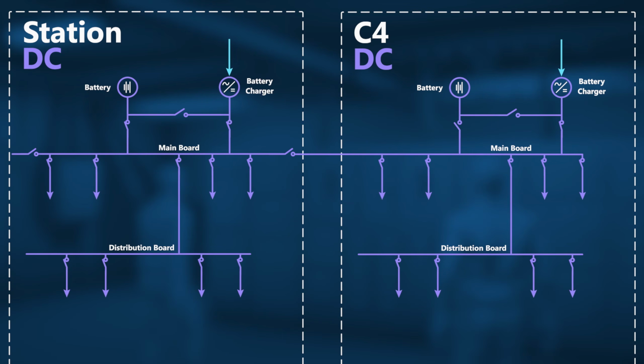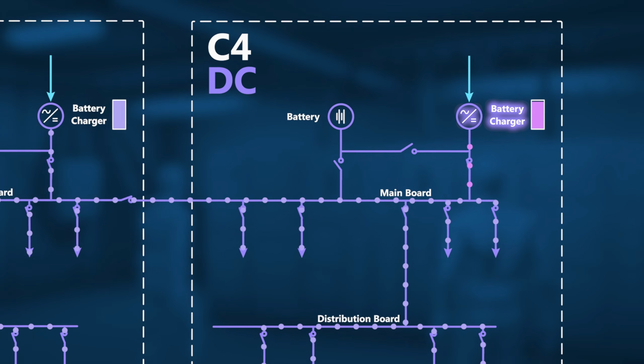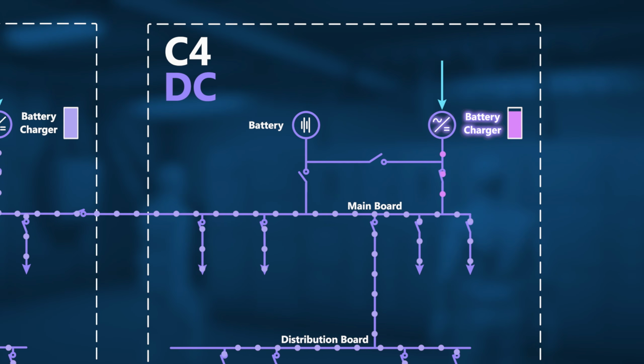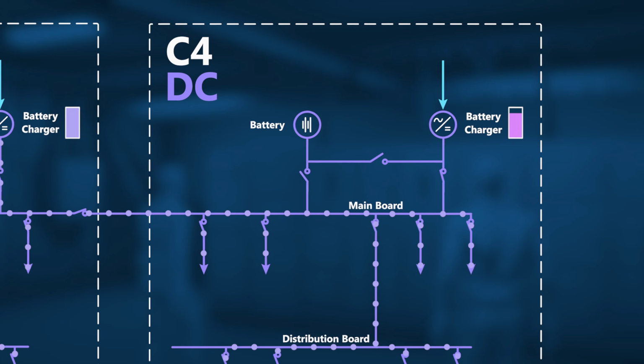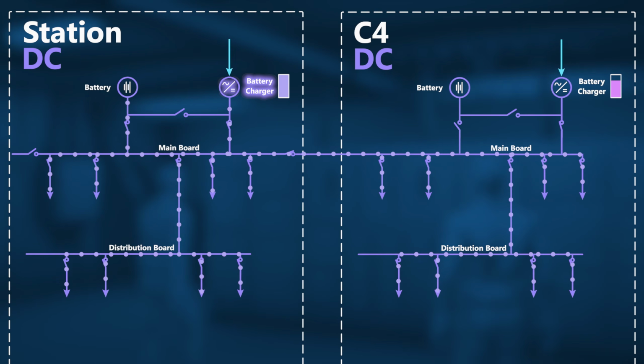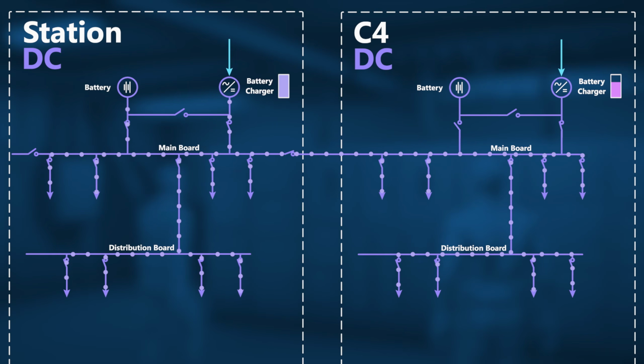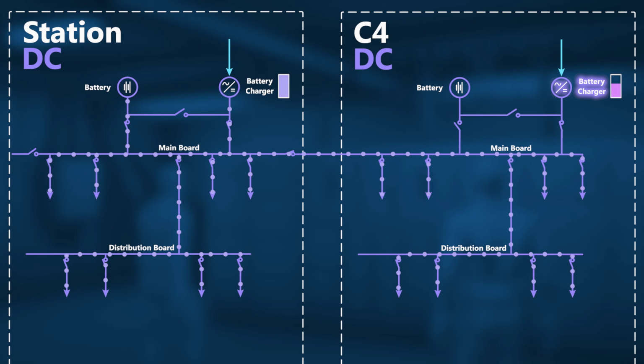To understand why, let's look at how the C4 and station battery chargers behave when they're connected to the same system. Before being connected, each battery charger maintains the voltage level in its respective DC system. This level is determined by each battery charger's configured output voltage. But when they are connected together, it's only the charger with the higher output voltage that supplies the system, lifting the voltage to this level. Meanwhile, the lower output charger detects that the voltage level in the system has increased and responds by decreasing its own output. Since the higher output charger continues to maintain the system voltage at this higher level, the voltage inside the lower output charger continues to decay.